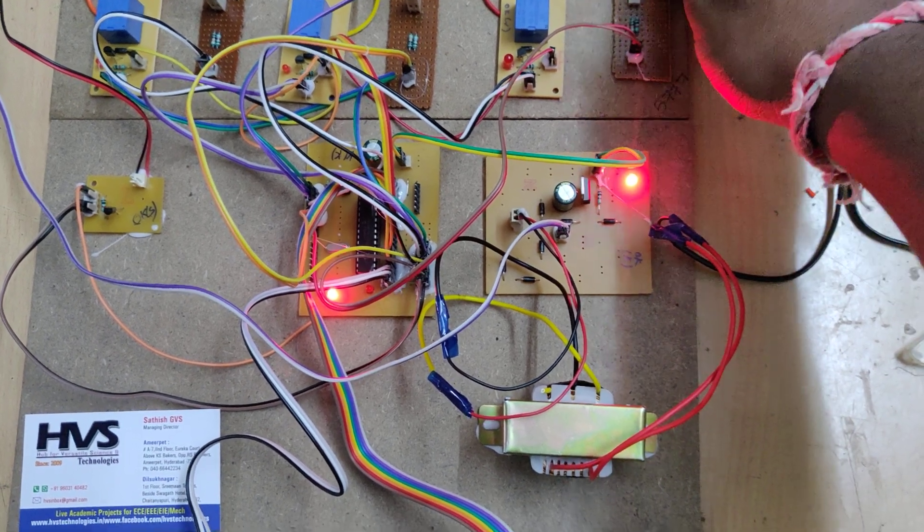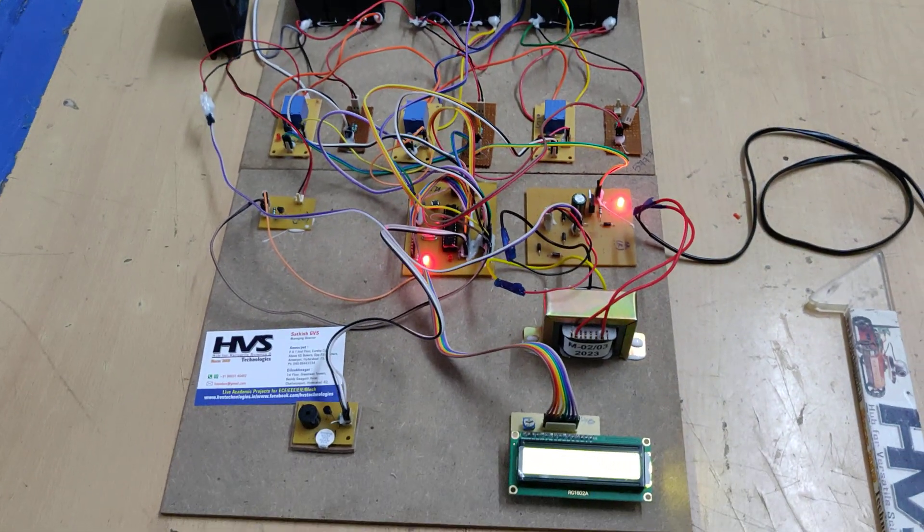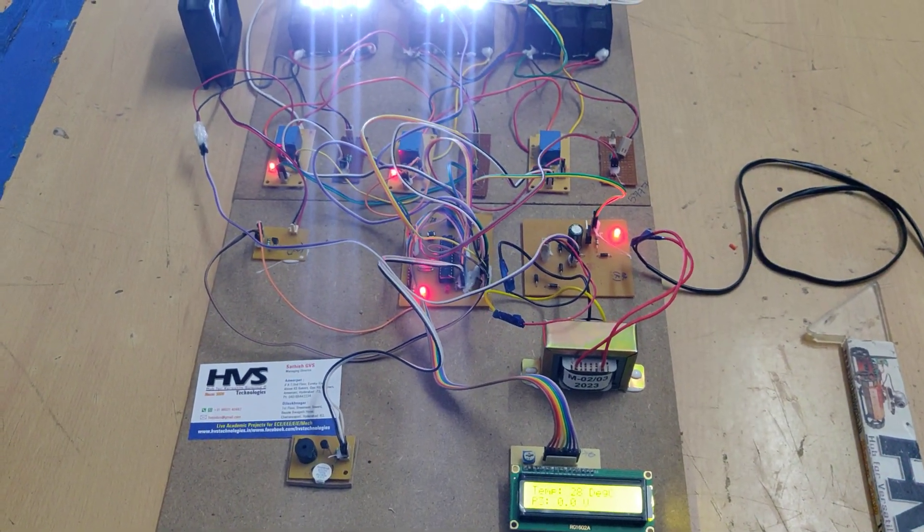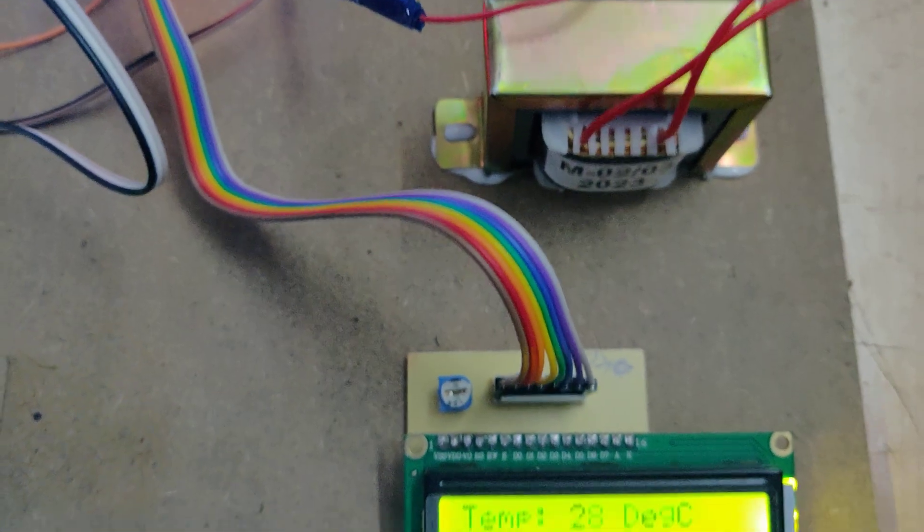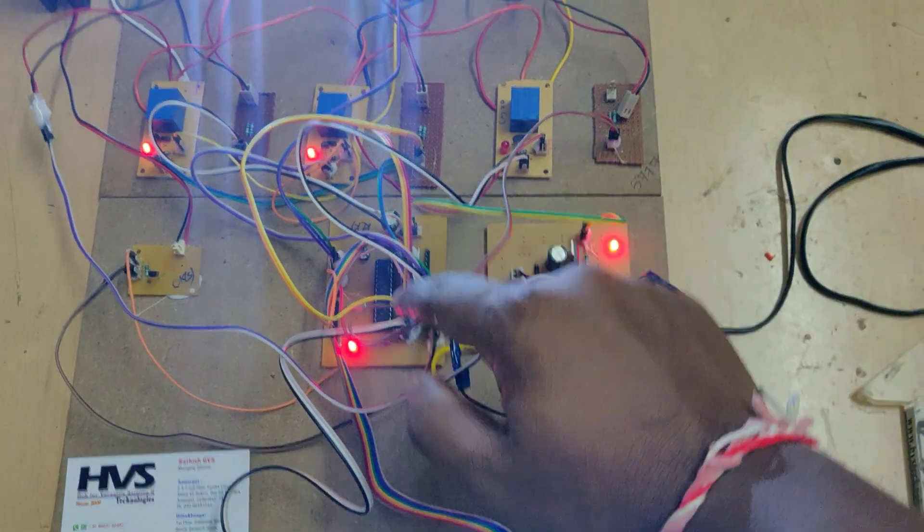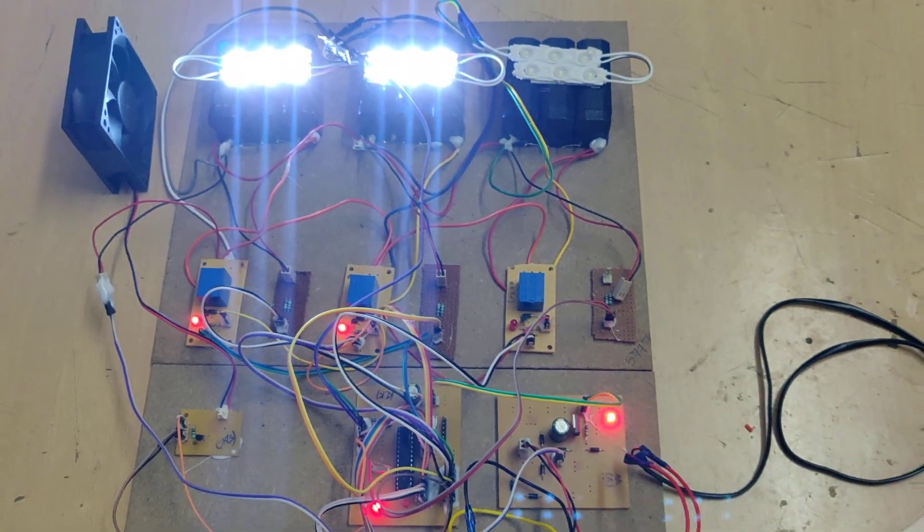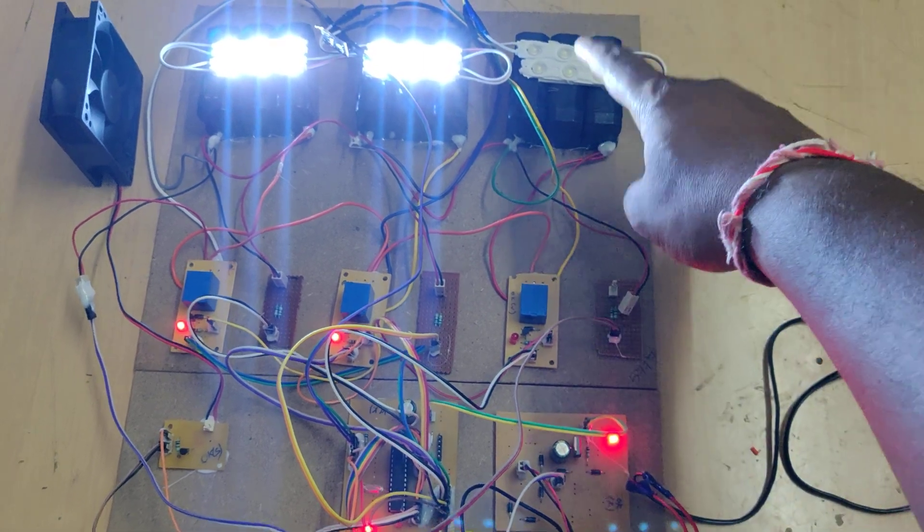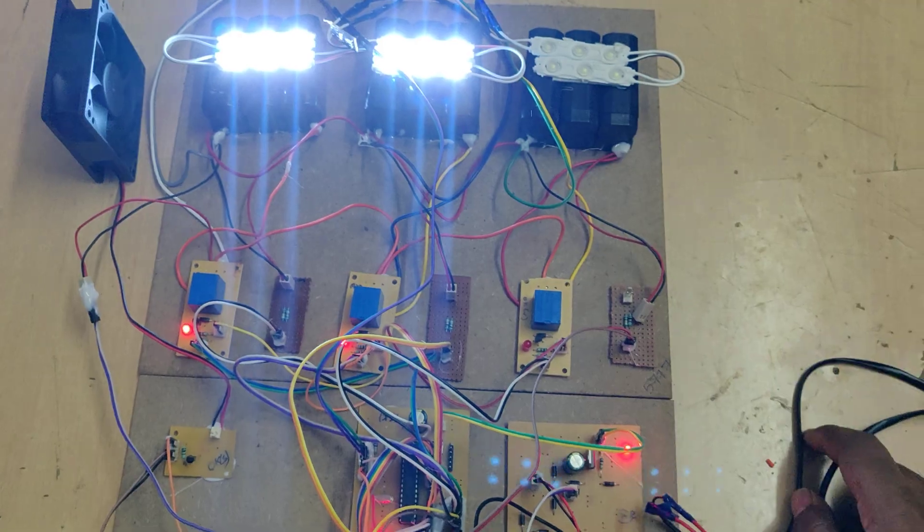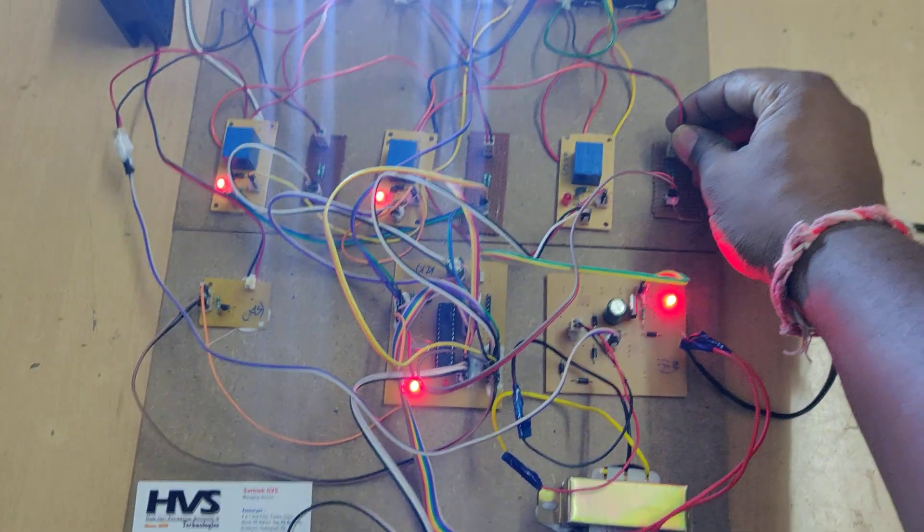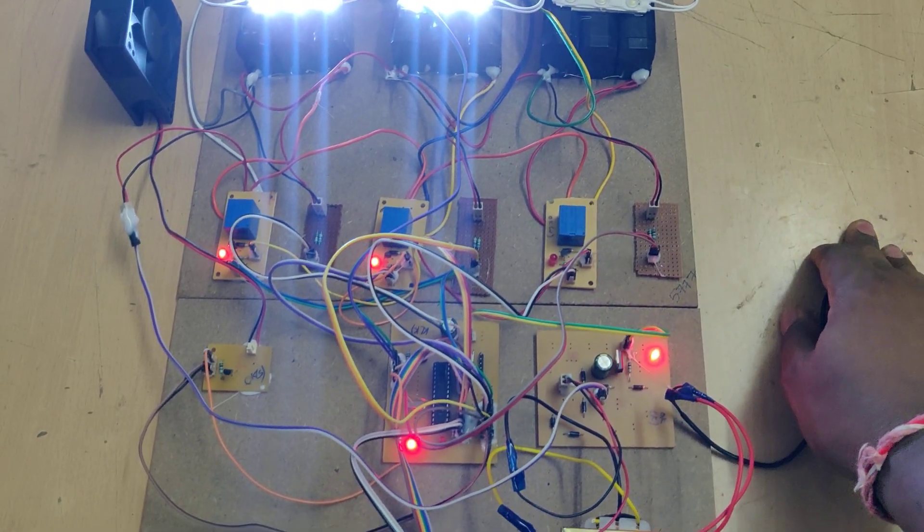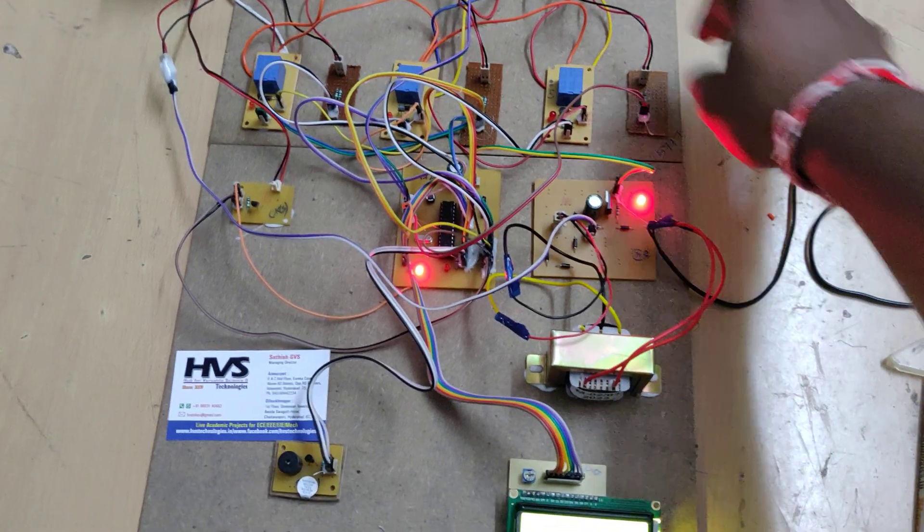When we isolate battery pack 3, the microcontroller will automatically turn on the loads to battery pack 1 and battery pack 2. As I isolate battery pack 3, the controller is trying to reduce the voltage of the remaining battery packs by adding the load only. Because it already has low voltage, it won't turn on the load to this one. The remaining loads will turn on and try to reduce the respective voltages. Now turn this back.